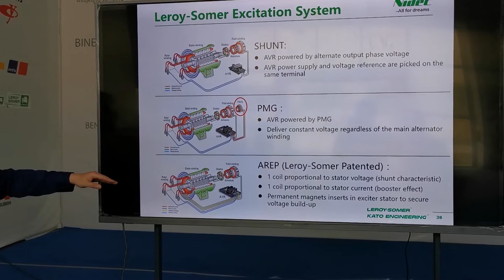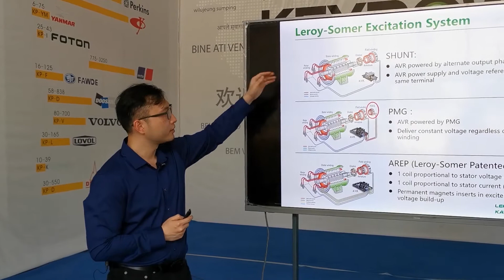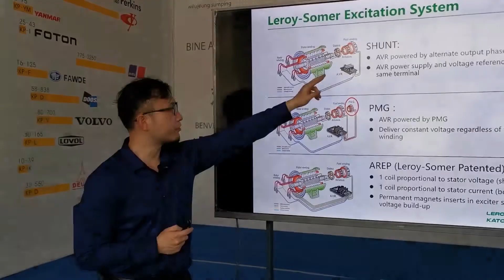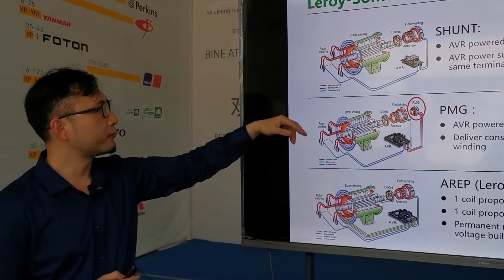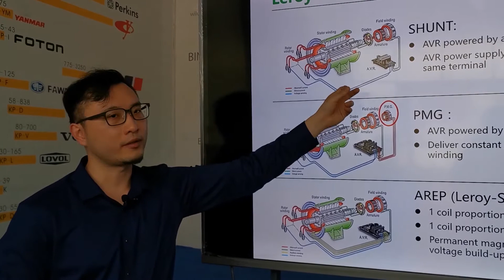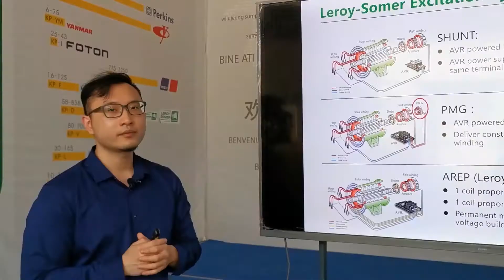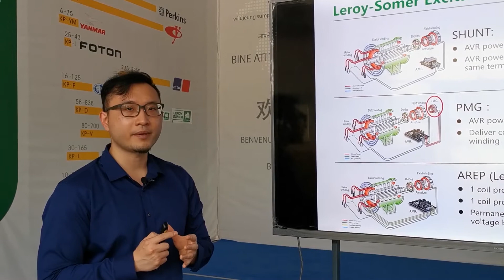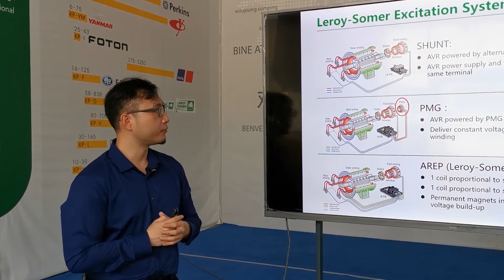If we simply define these 3 excitation systems, we can say that the main difference is the way the AVR is powered. For shunt, for example, the AVR will be powered by the alternator phase voltage, which means that if a short circuit happens for such an alternator with a shunt excitation system, the phase voltage will be 0, so the AVR will not have power. It cannot work. So we say that an alternator with shunt will not have short circuit current sustainability. And normally we will not recommend applications, for example parallel applications, to go with a shunt excitation system.